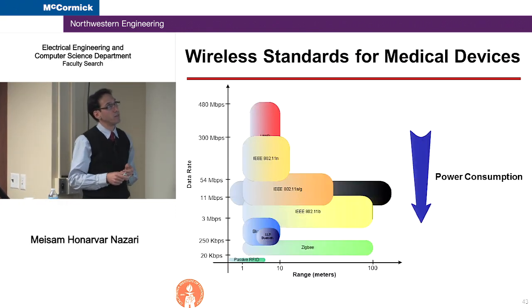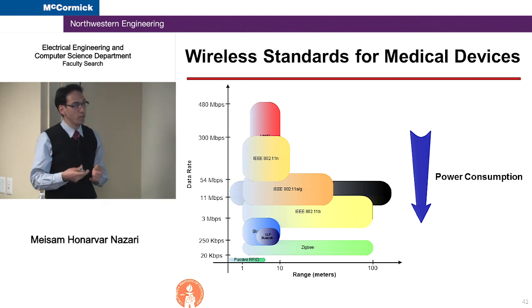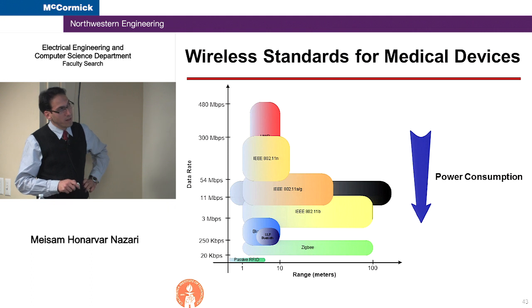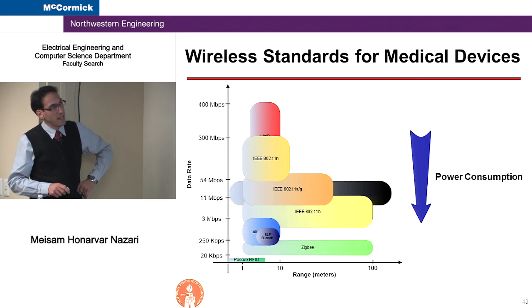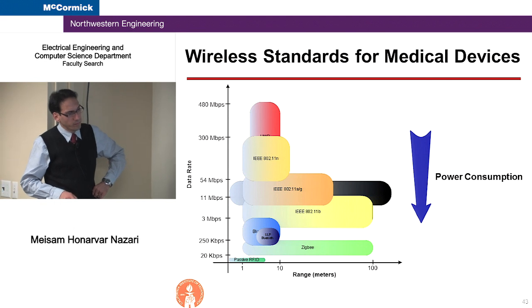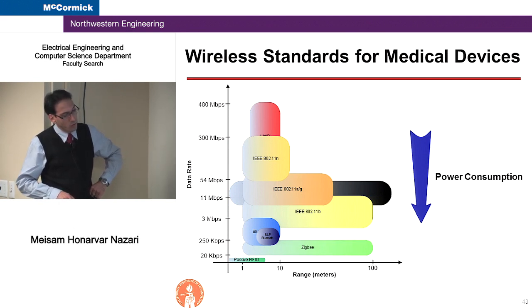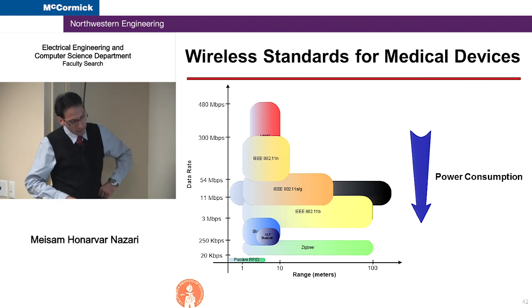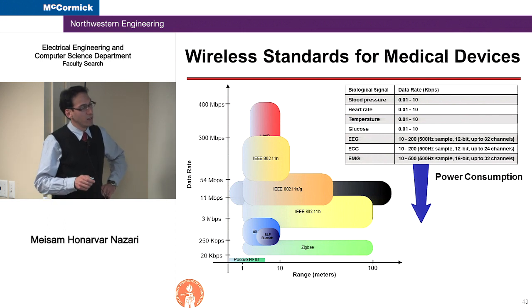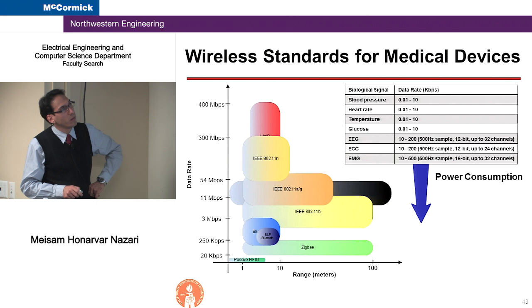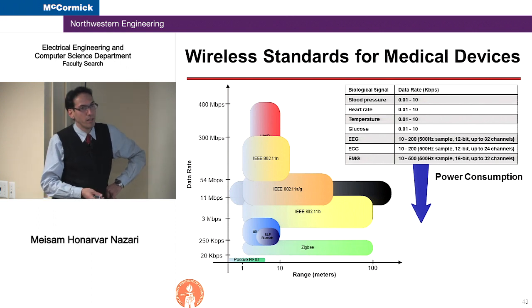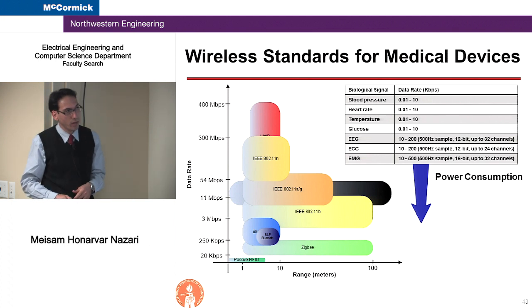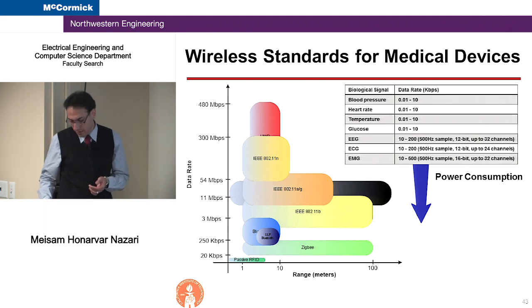The other thing to be considered is to find a way to communicate between the device and the outside world. This graph shows the standard wireless standards for medical devices. As you can see, the power becomes smaller and smaller as we go to lower and lower data rates. It's interesting that for biological signals, we do not need very high data rates. So we have adopted a passive kind of communication between the implant and the outside world. That's in our favor because it gives us the smallest power consumption.